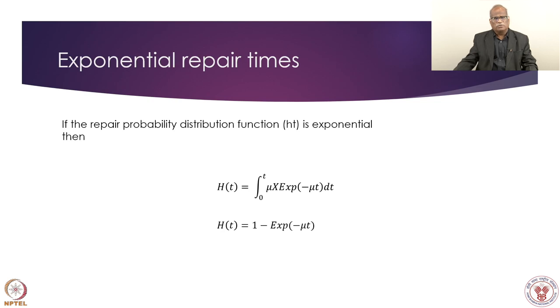For individual models, the exponential model is the simplest. The cumulative density function for repair time is given by integrating from 0 to t: μ·e^(−μt) dt, which gives H(t) = 1 − e^(−μt). This is indeed a very good maintainability function expressed as a cumulative density function. We have thus covered maintainability as an introduction: the role of repair time distribution, PDF of repair, mean time to repair, and the cumulative distribution function of maintainability.